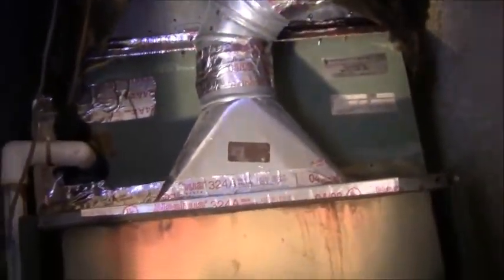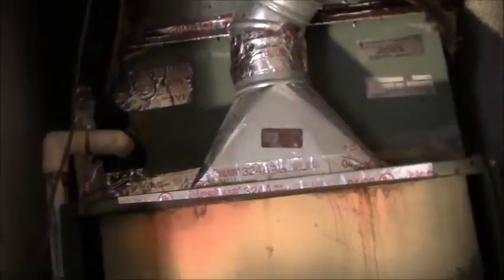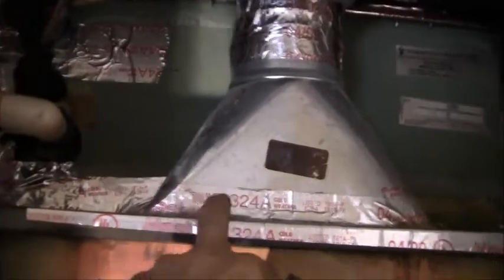So then that comes up to this point, and then from here it goes into your B vent stack, and then up and out of the residence at the roof level, okay? Outside the house. You don't need a draft hood like you do on a hot water heater at this location, because the draft hood on this furnace is right here.